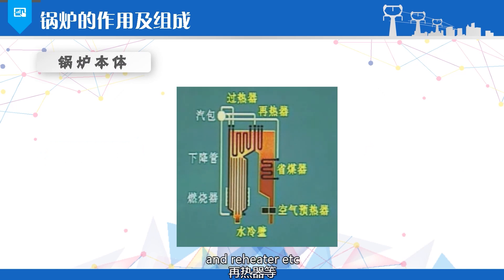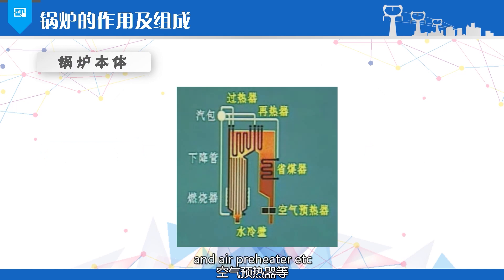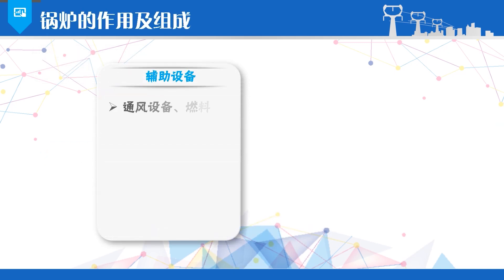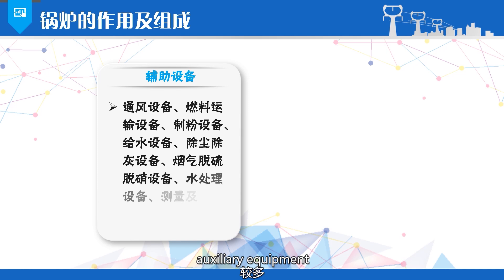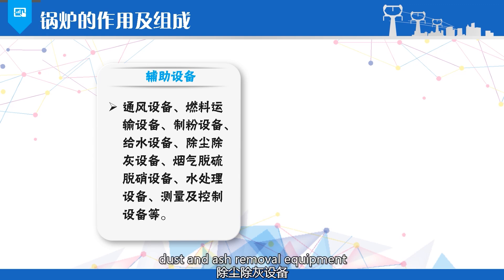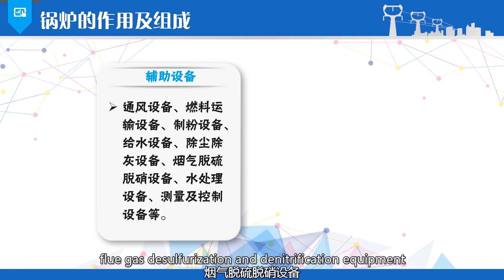The economizer, steam drum, downcomer tubes, water-cooled walls, superheater, and reheater form the pressure part of the boiler, while the furnace, flue ducts, burners, and air preheater form the combustion part of the boiler. Additionally, the boiler body also includes the furnace wall and the structure. Power station boilers have a considerable number of auxiliary equipment, which mainly include ventilation equipment, fuel transportation equipment, pulverizing equipment, and feed water equipment.